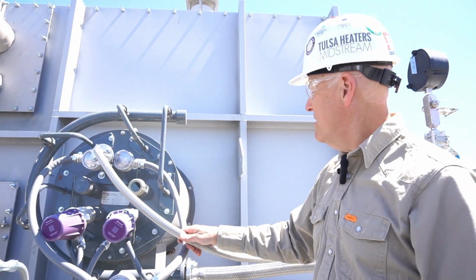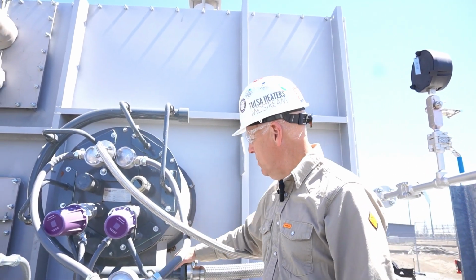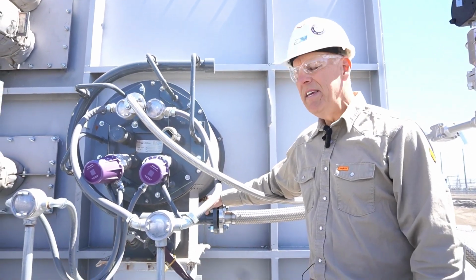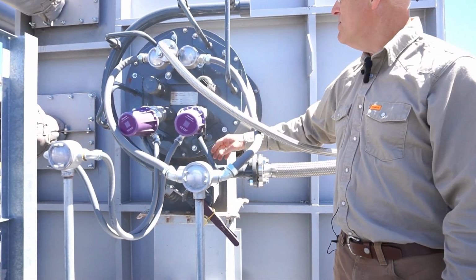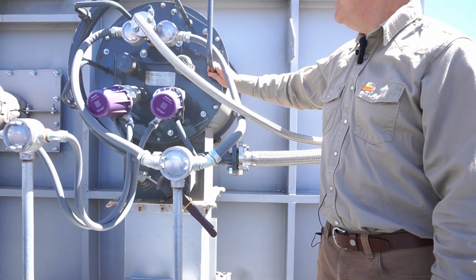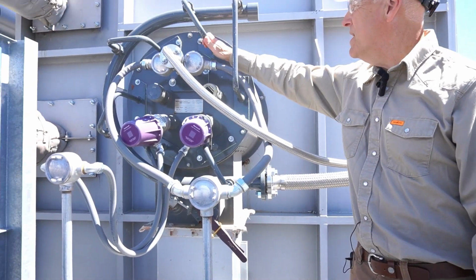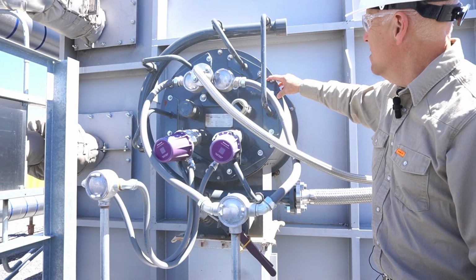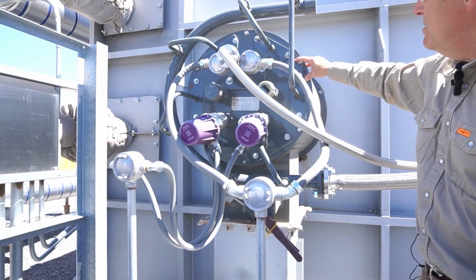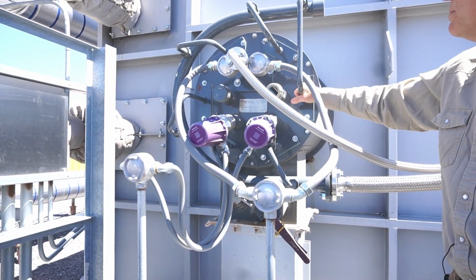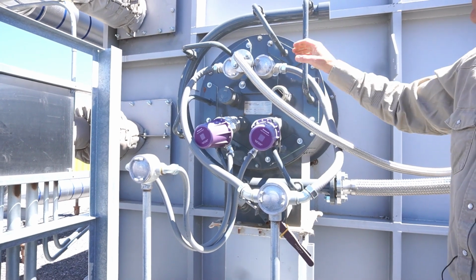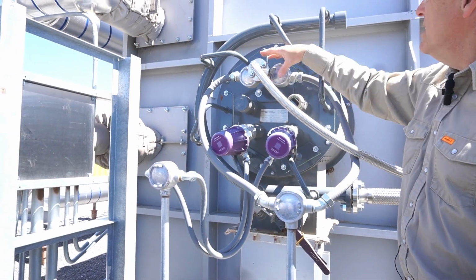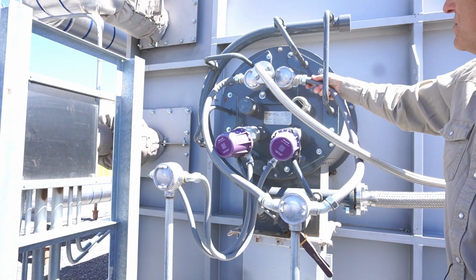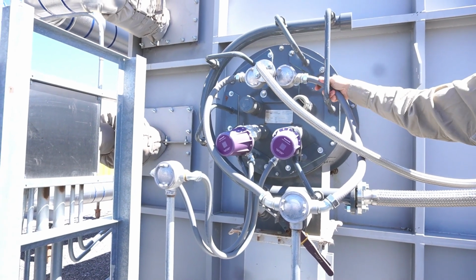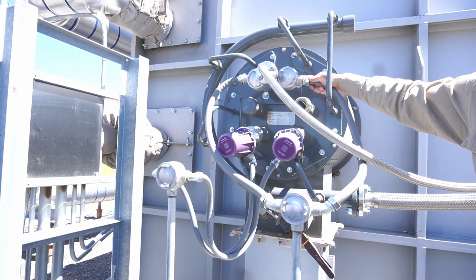So looking at the other main components of the burner, we've got the main gas coming in here, and these little takeoffs, these are the gas guns themselves. So you can see that this particular burner has, it looks like, 8 gas guns. It's an ultra low NOx burner. It's got obviously the pilot gas going in. One of these lines is for the flame ionization rod, but the other is to actually light the pilot.